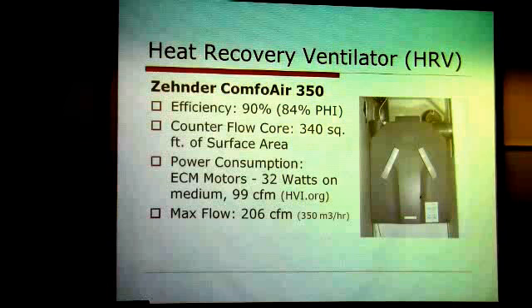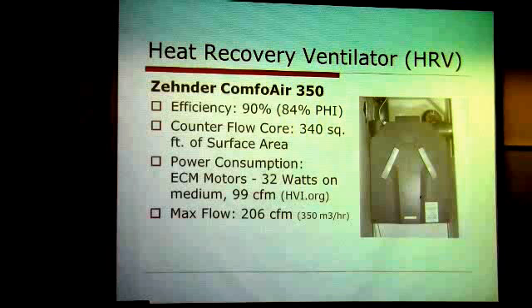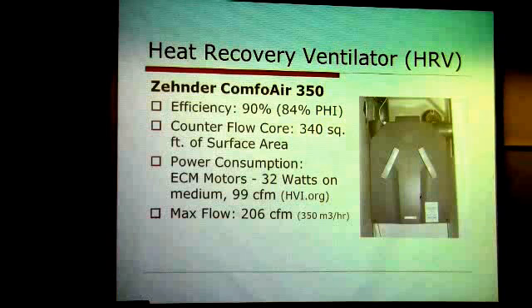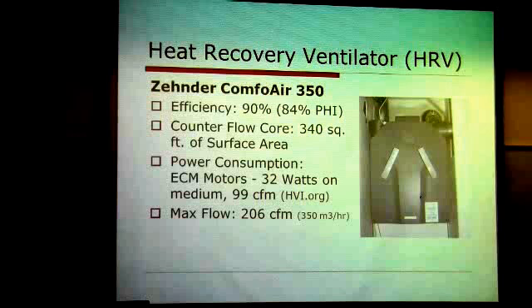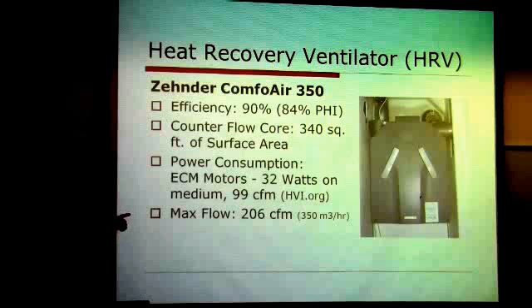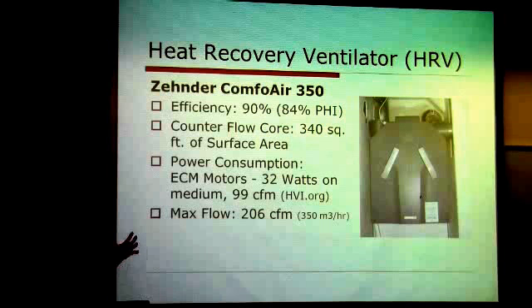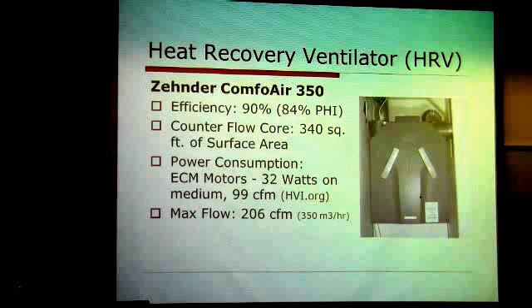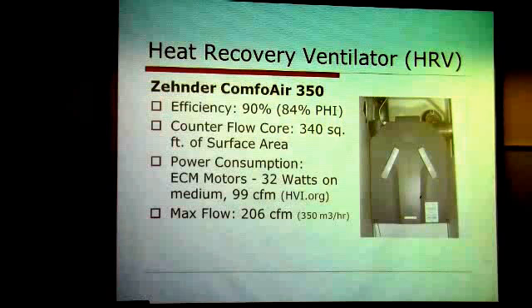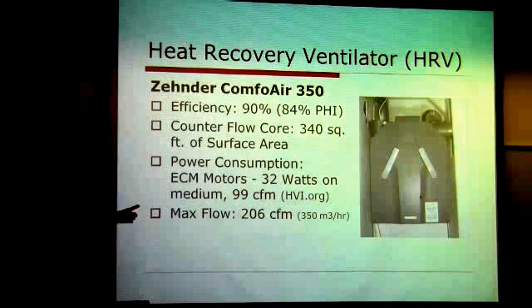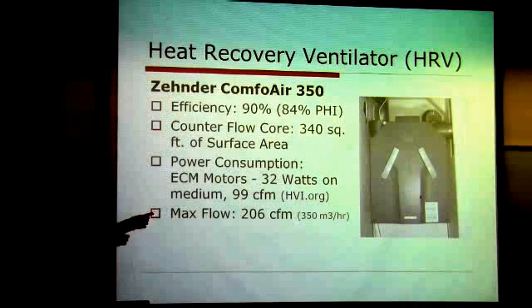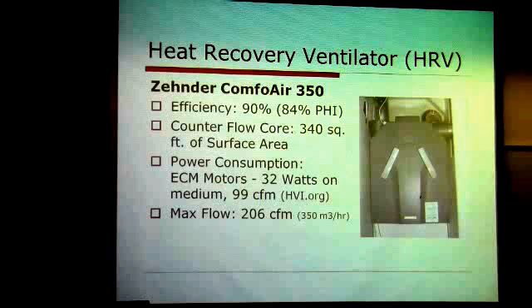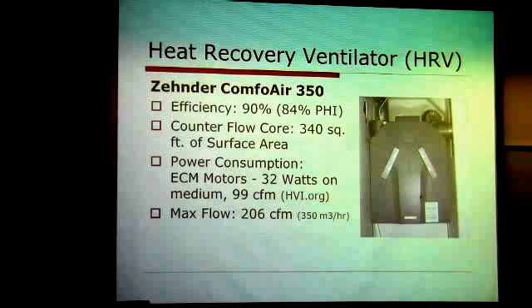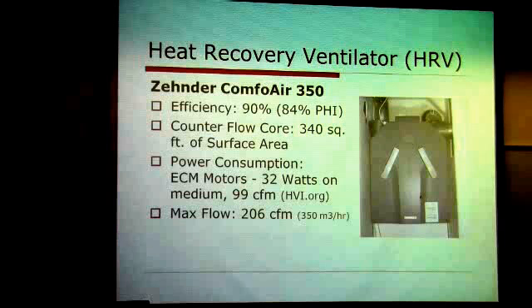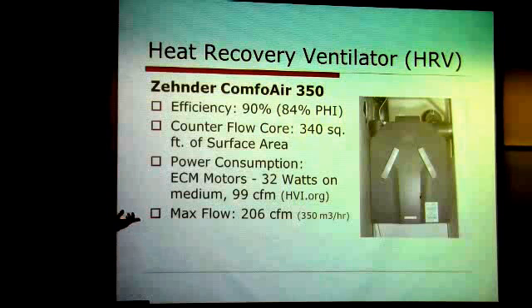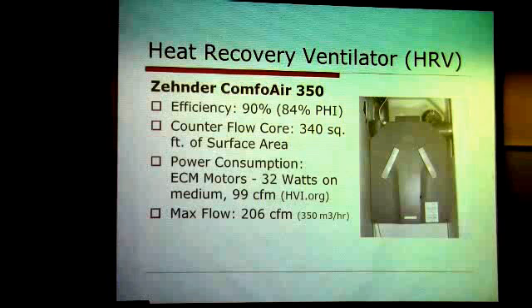Passive House Institute grades it a little differently. It takes the average of 3 very low temperatures and then subtracts off the wattage. Here we had it tested at HVI, which tests a lot of bath fans. If you go into their website, it compares bath fans in one section and a lot of HRVs, ERVs in another section. On their tests, this was pulling in 32 watts on a medium speed, and the flow rate was 99 CFM. The max flow rate on this unit is 206, and the 350 comes from 350 cubic meters per hour, which is the European metric system.